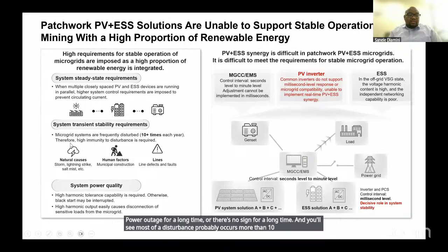What does this mean? It means that the patchwork, we're talking about you've got different products from different suppliers. So you will actually have probably higher requirements of stable operation of the microgrid. So you will see that most of the time the system itself will actually need something to prevent circulation current. Probably you'll need something like your PV, your BESS, probably also a generator in case there's a power outage for a long time or there's no sun for a long time. And you see most of the disturbance probably occurs more than 10 times a year. That is caused by your storm, lightning strike, and the salty mist in those areas. And human factors and also line defects. The lines, they also got defects.